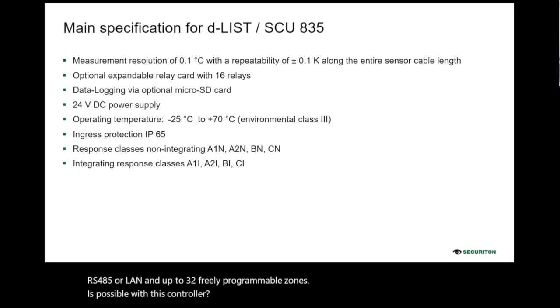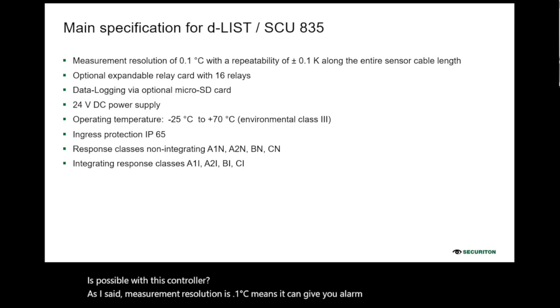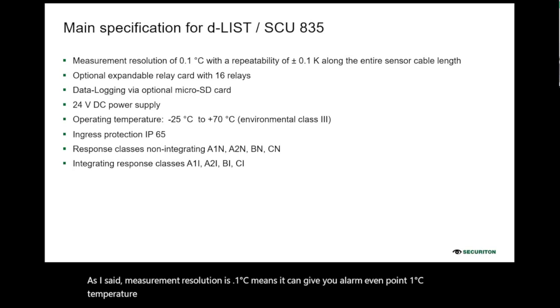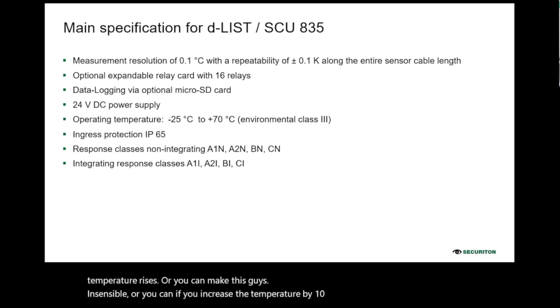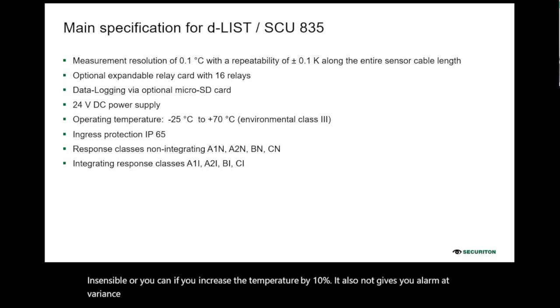As I said, measurement resolution is 0.1 degree centigrade, which means it can give you an alarm even if the temperature rises by 0.1 degree centigrade. Or you can make it less sensitive, so that even if the temperature increases by 10%, it does not give you an alarm at a very incipient stage. So everything is possible because these cables are programmable.